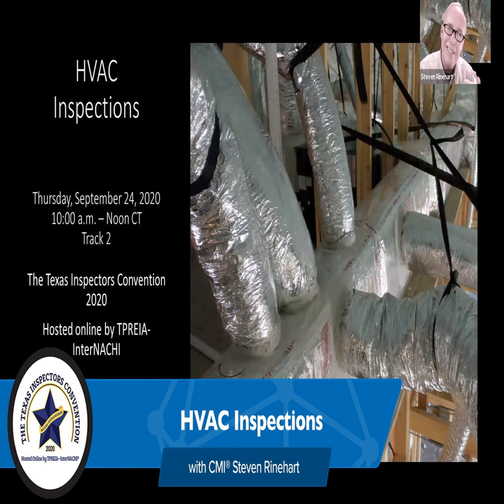Late 80s, we start coming out with a better flex duct, and that's kind of what's been used since then. Problems and damage is usually snagging, pulling it apart, holes. That vapor barrier on the outside is just that, a vapor barrier. The air is sealed in a liner, like a big 6-inch vacuum cleaner hose on the inside. Usually the damage you get to those is physical damage from somebody stepping on it, sitting on it.